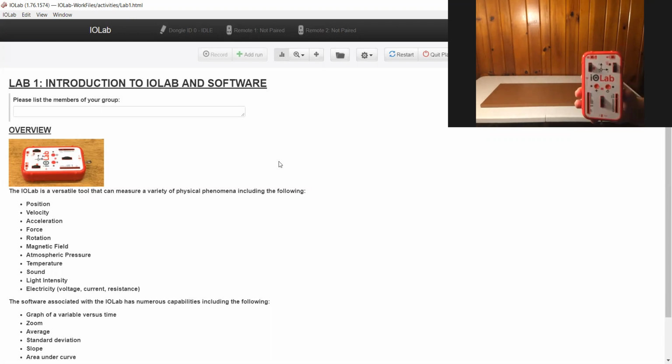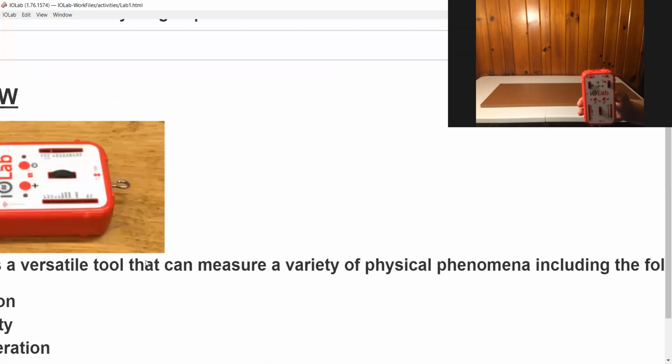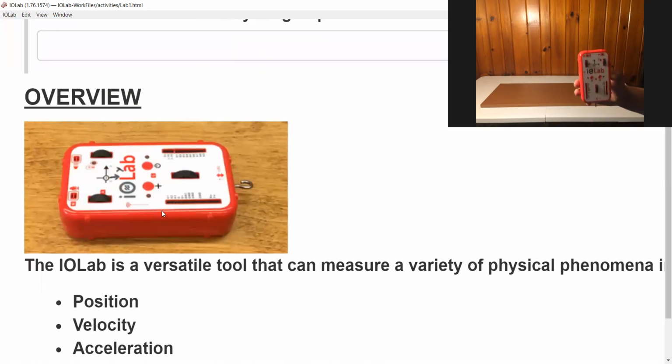One interesting thing to point out is the difference in the direction of the positive y-axis in the software, which they have considered. On the device, the direction of the positive y-axis goes from the single wheel towards the double wheel, going up. But in the software application, the file has been written in such a way that the positive y-axis goes from the double wheel towards the single wheel.